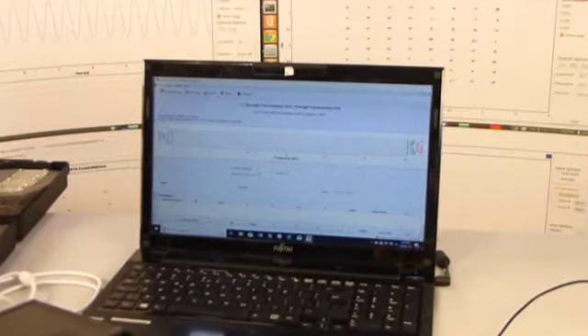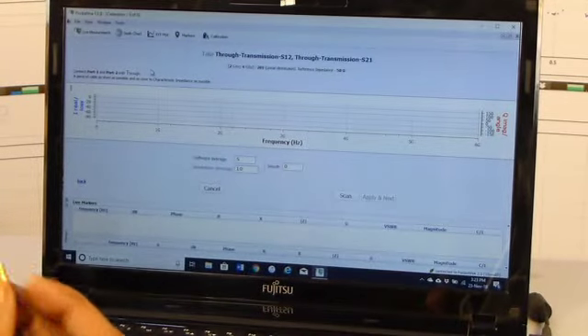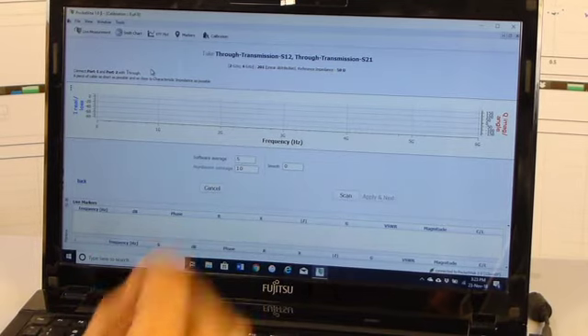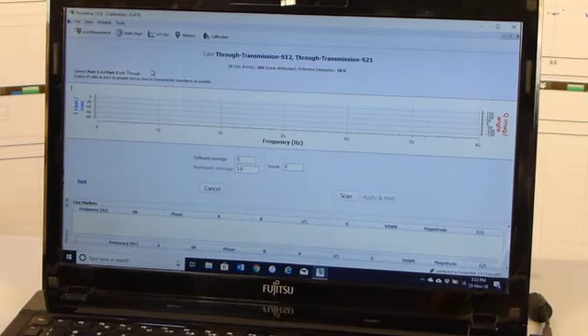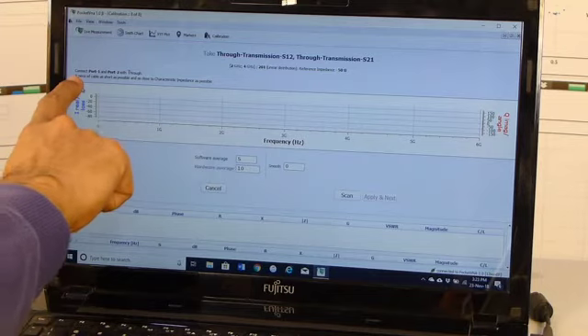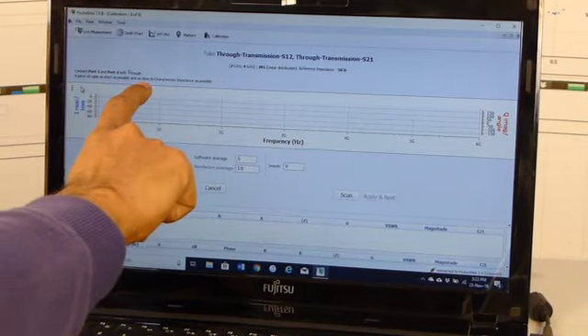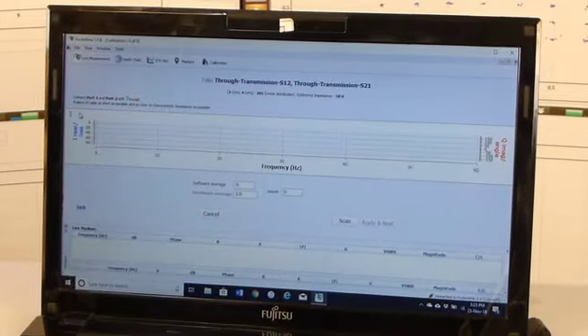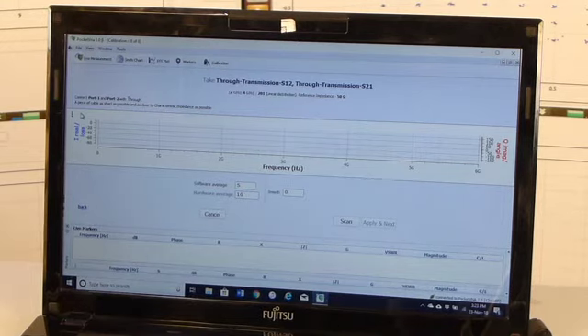Now this is the 8th step of the calibration. It says connect port 1 and port 2 with through. Now this is the through. This is a through connector. So here it is saying a piece of cable as short as possible and as close to characteristic impedance as possible. Now here the characteristic impedance is 50 ohm and this is an RG316 cable. So it has a characteristic impedance of 50 ohm up to 10 gigahertz.